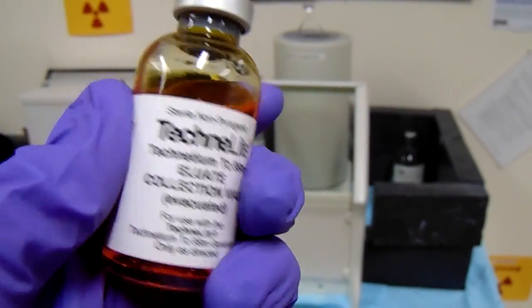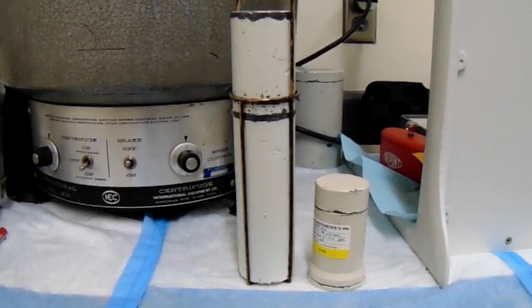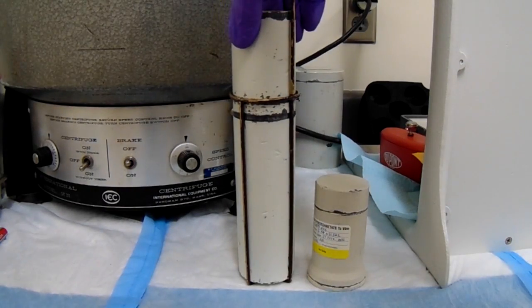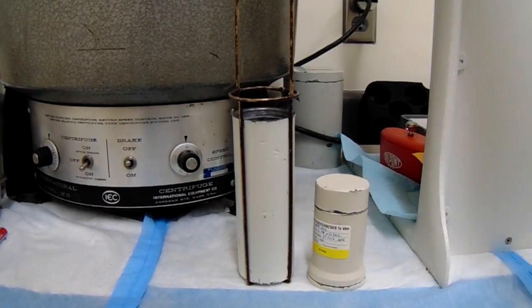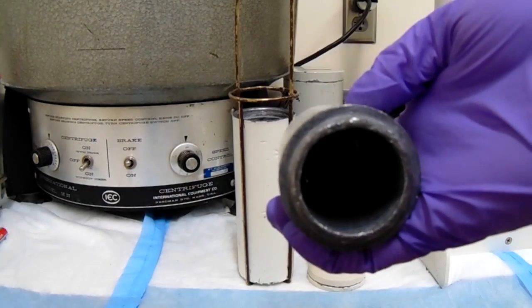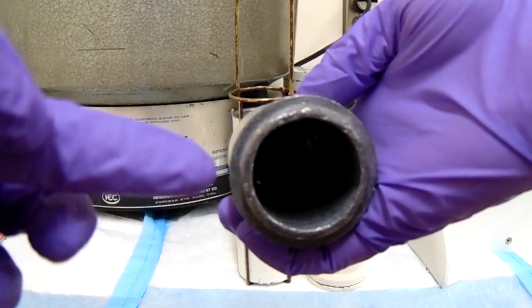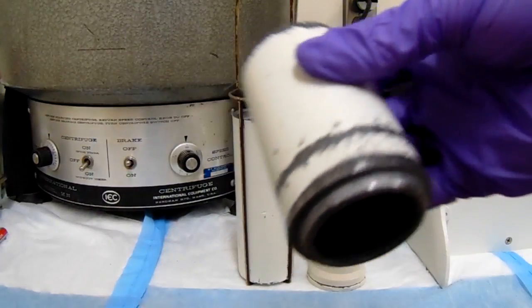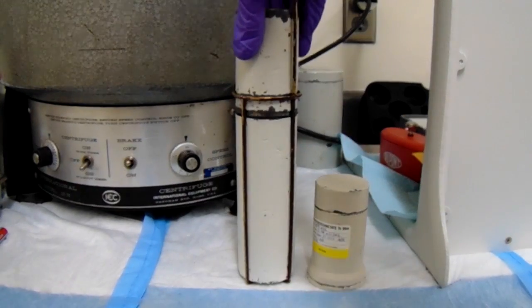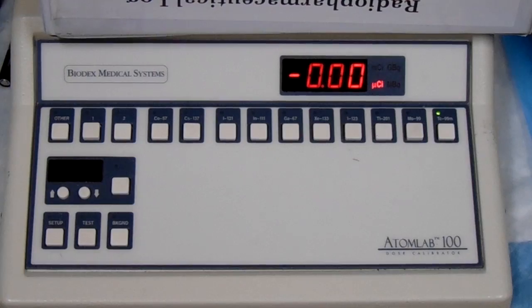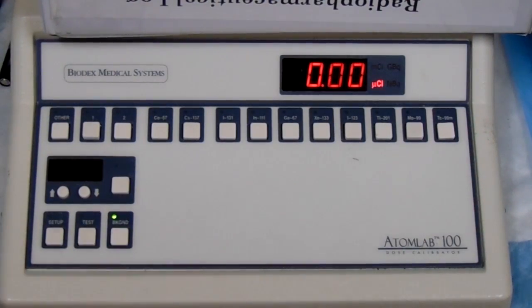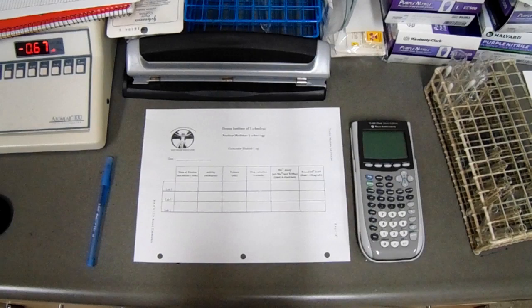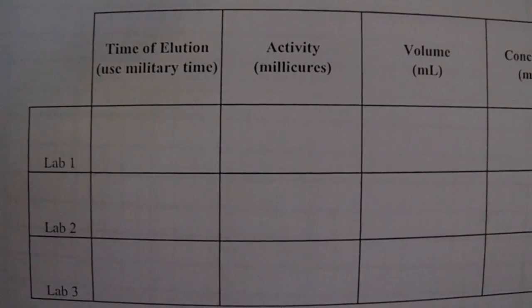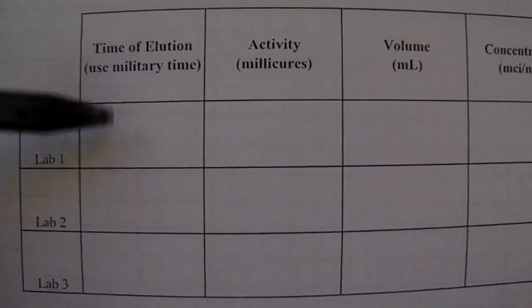So in order to do the molybdenum test, we need to use our moly pig. Our moly pig has 6 millimeters thick of lead in order to shield out any 140 keV technetium photons, while not being thick enough to block any of the high energy molybdenum gamma rays. First we're going to hit tech and do a background on our calibrator. This piece of paper is what we'll be recording all our values on. The first thing we're going to put down is the time that we eluted the generator.